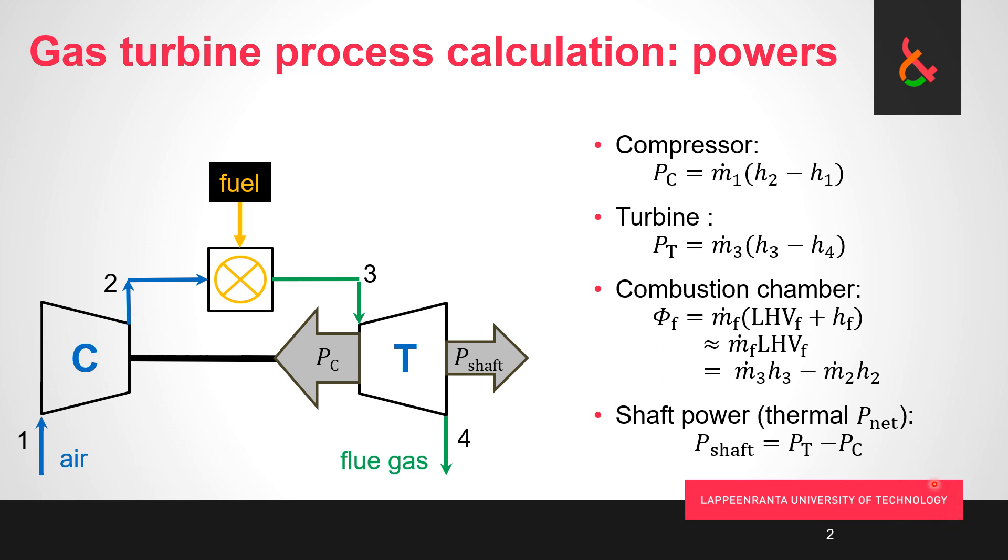Then we have the net thermal power or the shaft power of the gas turbine, and that is going to be the thermal power of the turbine, what the gas leaves to the turbine rotor, minus the consumption of the compressor. So roughly half, rather more than less than half of the turbine power is used to run its own compressor.